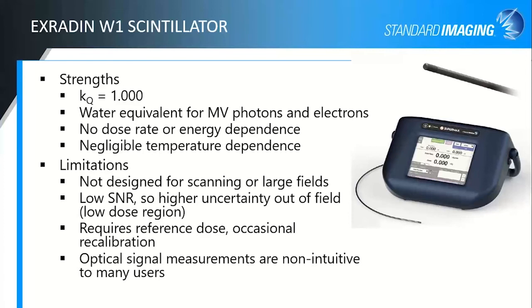As we mentioned about the scintillation detectors, you do have to give it a reference dose and occasionally recalibrate it. The other issue that we found with the W1 is that optical signal measurements are not intuitive to many users. We're very used to measuring with ion chambers. We understand diodes, and so when things don't look quite right, we have an idea of where to look. Whereas measuring optical signal takes a little bit more getting used to for some people. It's not bad. You can get over the learning curve fairly quickly, but when things don't look quite right, it does take a little bit more troubleshooting sometimes to figure out what's going on.